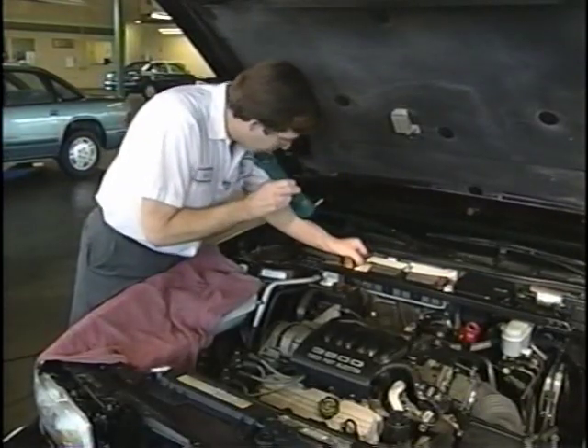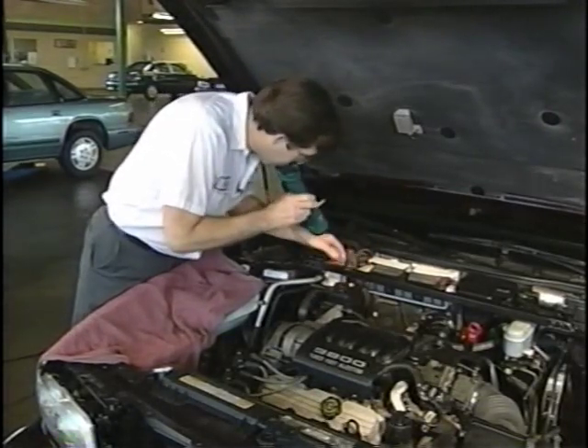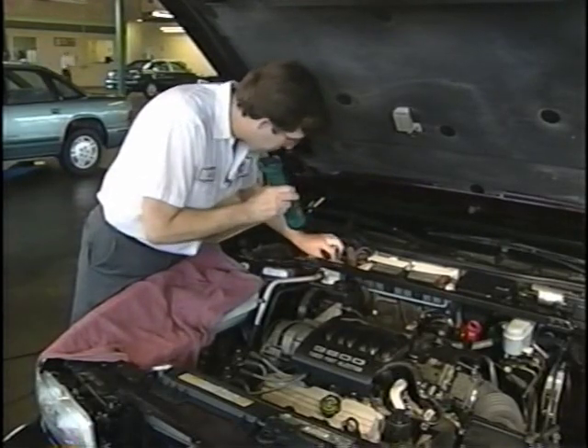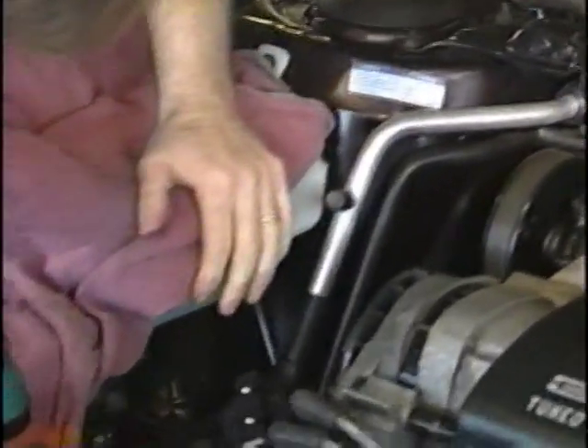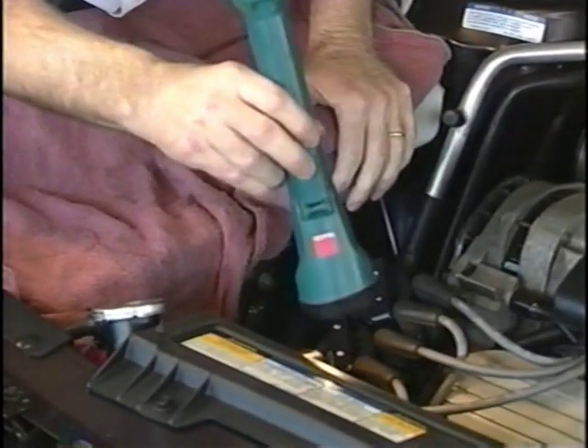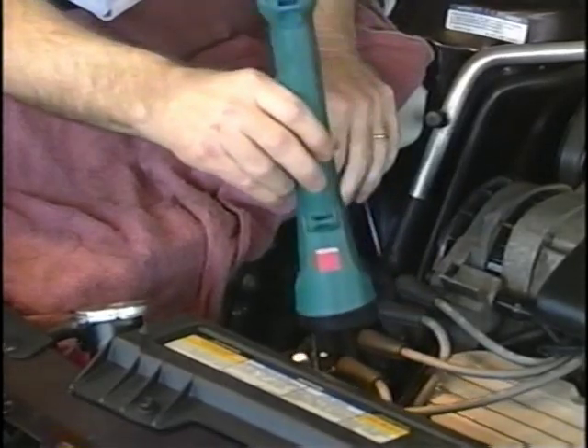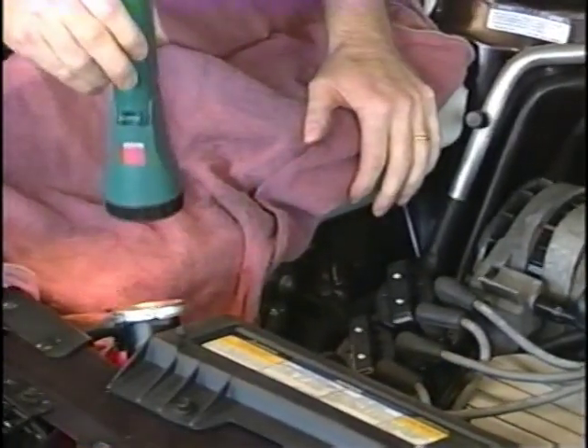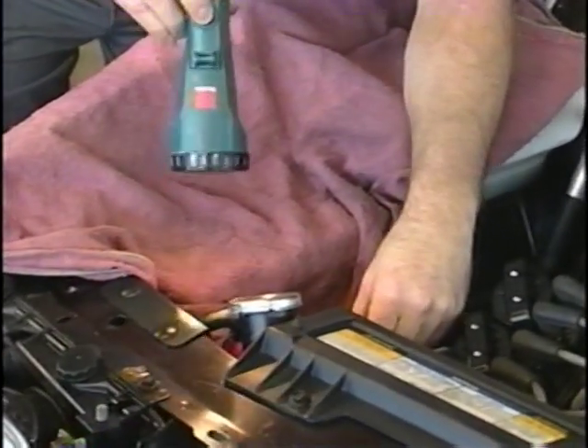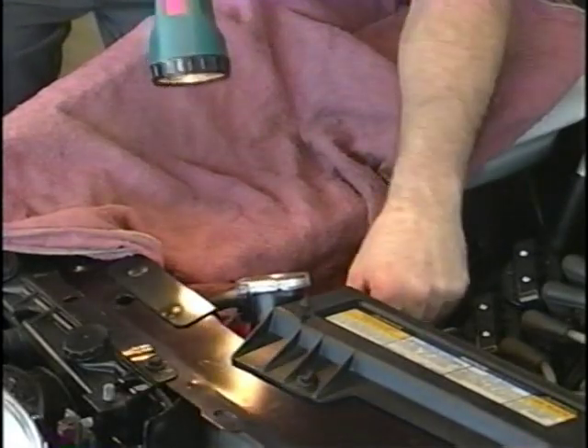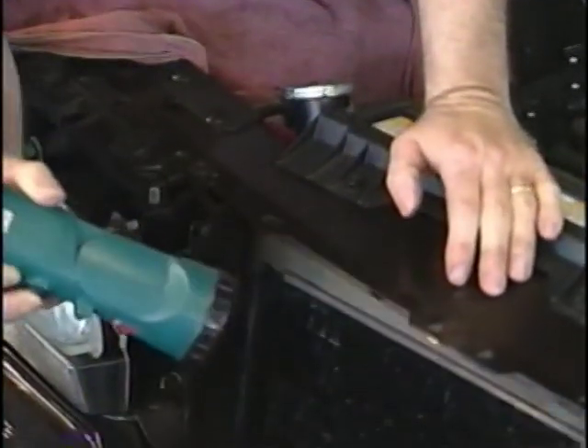Once you have a good idea there's a leak, the first thing would be to look it over visually as much as possible. The majority of the times you'll probably see some signs of it leaking, of the oil somewhere. Just watch the lines, the fittings, look for anything obvious, oil around the pressure switch. Follow the line all the way down to the compressor. Look at the hose ends down there and the switch down there at the compressor, and then follow it back up to the condenser. Look down the side of the condenser, see if anything looks wet there. Look at the front of it for any damage, any signs of anything wrong there.